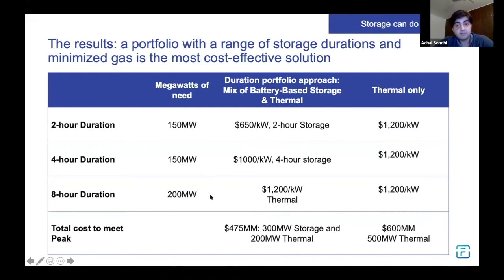But if you were to piece it out by duration—say I take a 2-hour, a 4-hour, and an 8-hour duration—I can meet the 2-hour and 4-hour duration with batteries at a lower price per kilowatt hour. Then the replacement is what we'd call our new peak for thermal, or our new base load. You end up with a bill that's much lower, so the consumer ends up with a lower cost on the grid. So just in pure economics, there's a benefit to doing such an analysis and seeing how you can meet the peak with storage.